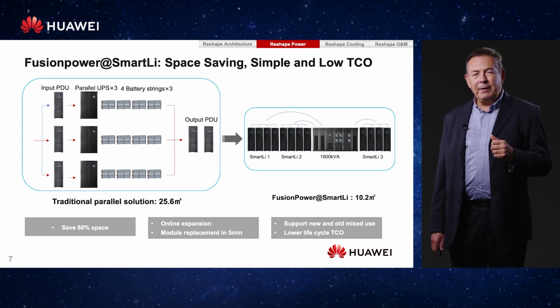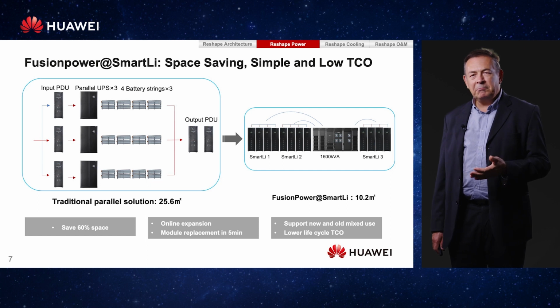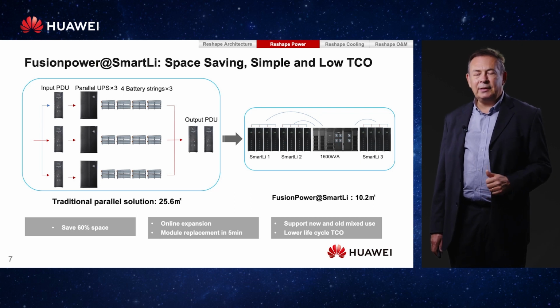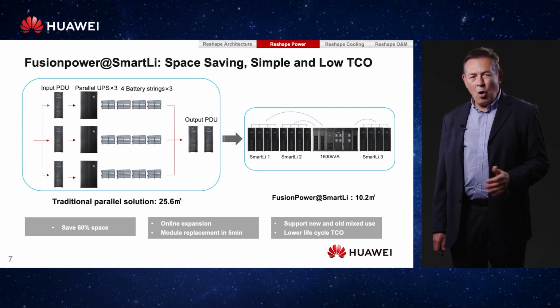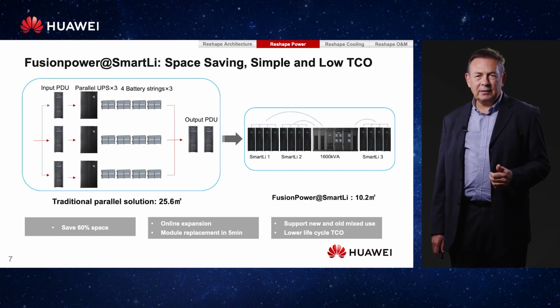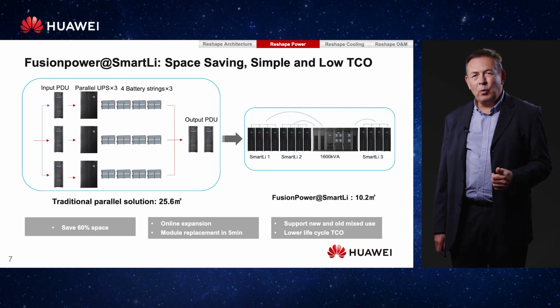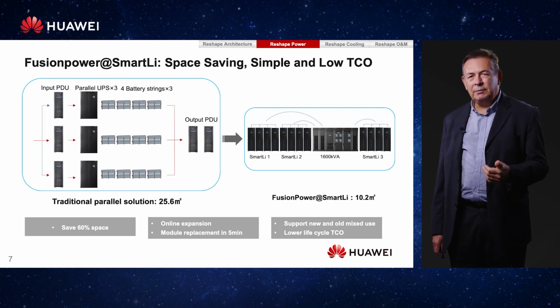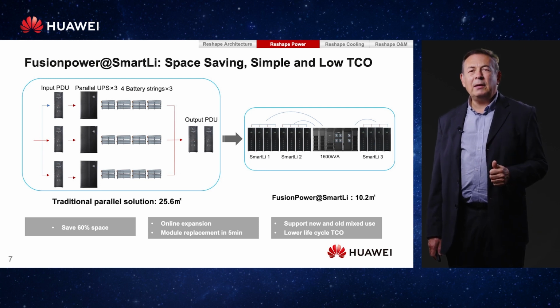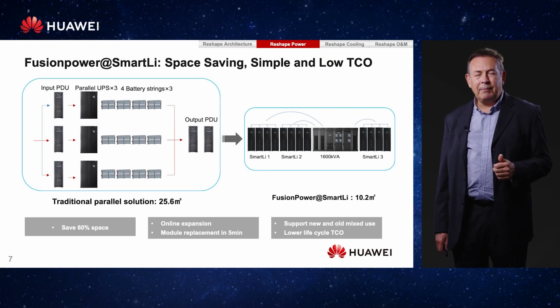This 1.6 megawatt UPS, traditionally, can be built using three times 800 kilowatt UPS, each with lead-acid batteries connected to the UPS. Or we can use a 1.6 megawatt fusion power UPS using the 100 kilowatt, very high efficiency 97% modules, together with SmartLi lithium-ion UPS batteries.